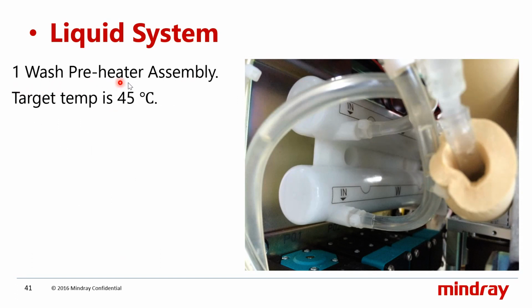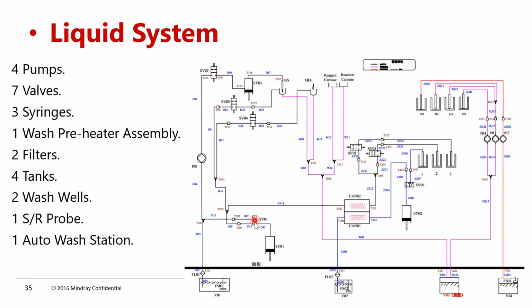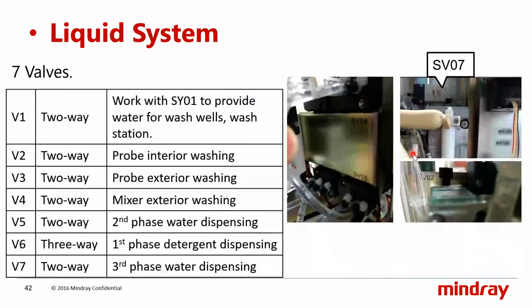So coming to the wash preheater assembly, it is an entirely single module. One line is for the wash water and the other line is for the detergent. This wash preheater assembly maintains a 45 degrees temperature. As we see in the diagram, this is the preheater assembly. One line is a wash water line, another line is a detergent line. And we have 7 valves. As I explained earlier, valve number 1 is for syringe 1. Valve number 2 is probe interior washing, 3 is for probe exterior washing, 4 is for mixer washing, 5 is second phase water dispensing, 6 is for first phase detergent dispensing, and 7 is for third phase water dispensing.